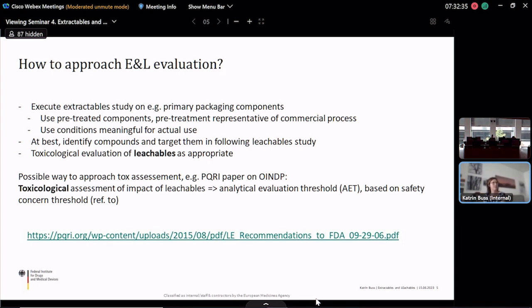When you have done this, you do your extractables study with representative extraction conditions. That means that you don't have to fully degrade your material. You don't have to do a fully exhaustive study, so that in the end perhaps your component is completely diluted. But it should be exaggerated compared to the actual intended use. Otherwise, it wouldn't be an extractables study.